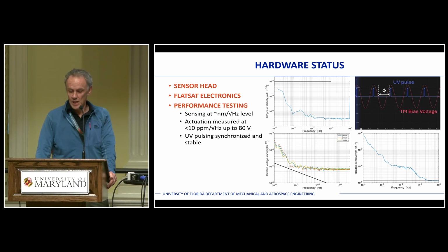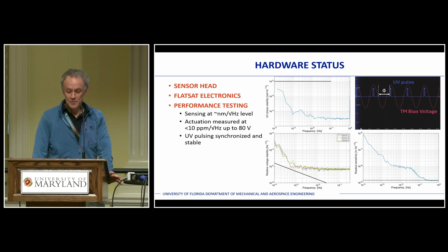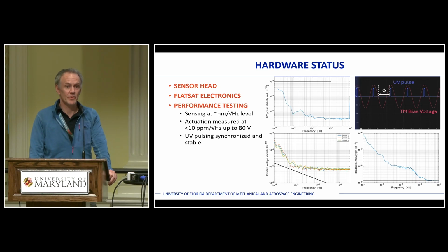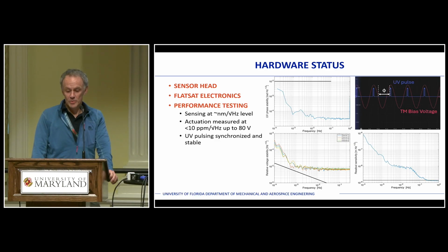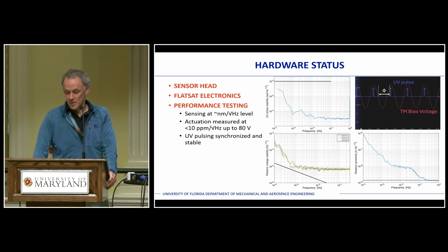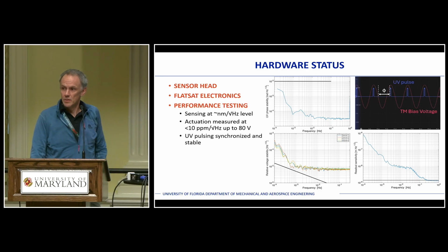On the bottom here, bottom left, we're measuring the actuation stability of the sensor voltages. That's really the critical performance driver for the accelerometer, and we're able to do better than 10 parts per million with an actuation of 80 volts. The capacitive sensing is also working to specification, around a nanometer per root hertz.